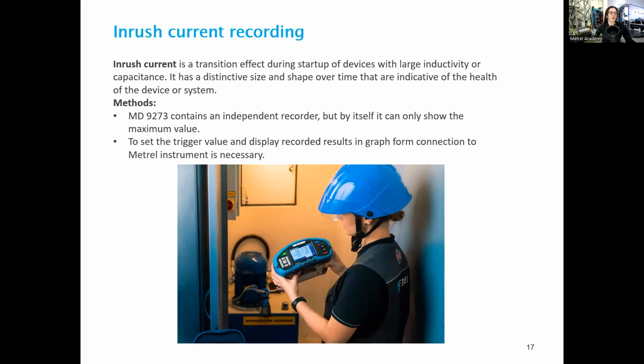Our next ability that we're going to present is inrush current recording. So inrush current is a very short and very high peak of current during the startup of electrical machines that lowers into operational value within a very short time. Its size tends to be tens of times the nominal value, and it happens both in case of inductive loads due to startup magnetic effects, and in case of capacitive loads as the capacitors charge.